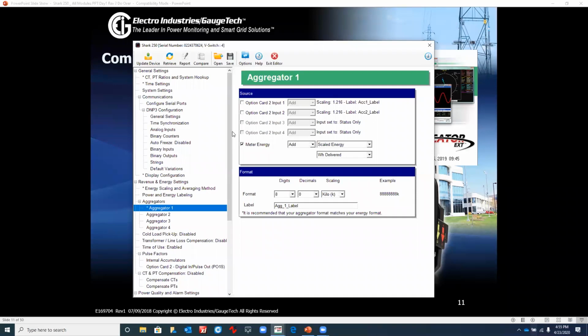But you can, oops, I take that back. I needed to record the meter energy. There I have, I can add or subtract functions in this aggregator portion. And here you have it, add or subtract. You could add energy values, and you have a choice of different quantities that you could pull down and aggregate onto one channel. And then you have your format of how many digits you want. Display would look almost like a separate meter, but you're adding up all the different points from the meter internally. So this is a nice thing to have for total aggregation of different data points within the meter.